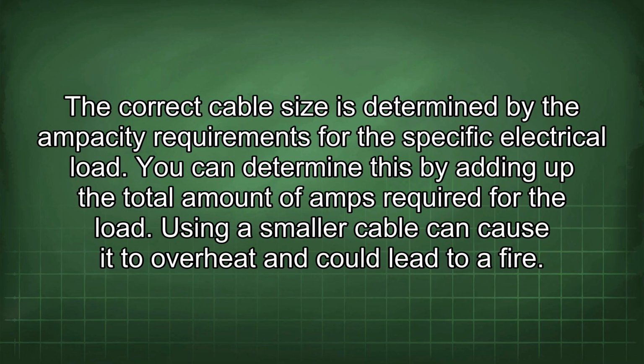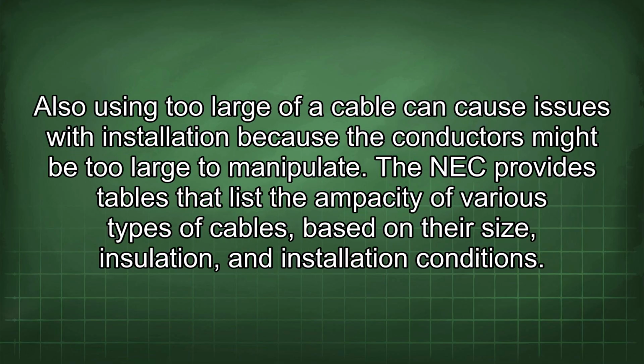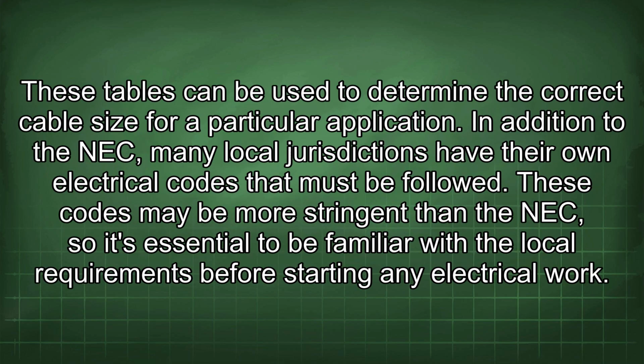The correct cable size is determined by the ampacity requirements for the specific electrical load. You can determine this by adding up the total amount of amps required for the load. Using a smaller cable can cause it to overheat and could lead to a fire. Also, using too large of a cable can cause issues with installation because the conductors might be too large to manipulate. The NEC provides tables that list the ampacity of various types of cables based on their size, insulation, and installation conditions. These tables can be used to determine the correct cable size for a particular application.